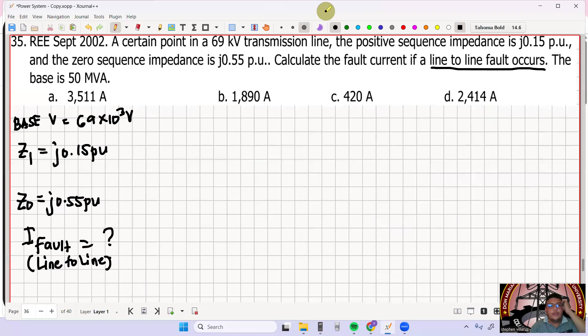Okay, paano natin yan kukunin? Take note for a line-to-line fault, ang ating I fault is equal to square root of 3 multiplied by E per unit all over Z1 plus Z2. Walang kinalaman dito yung zero sequence, okay?